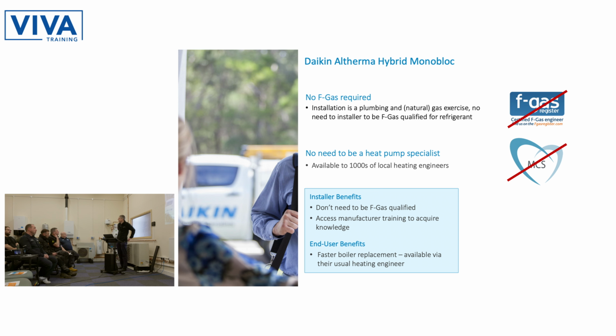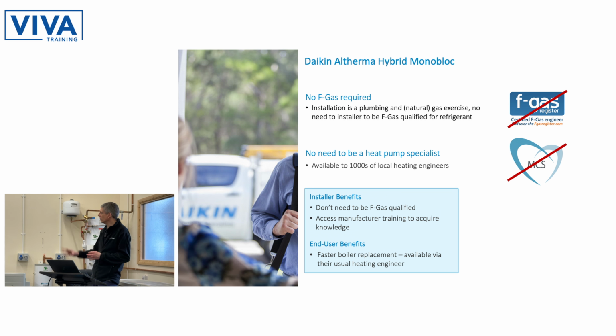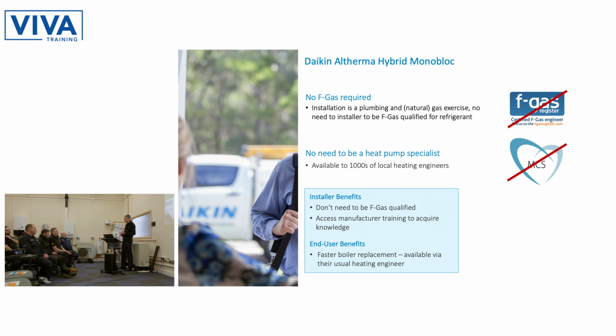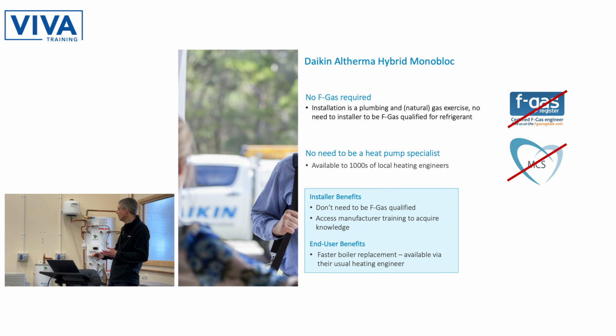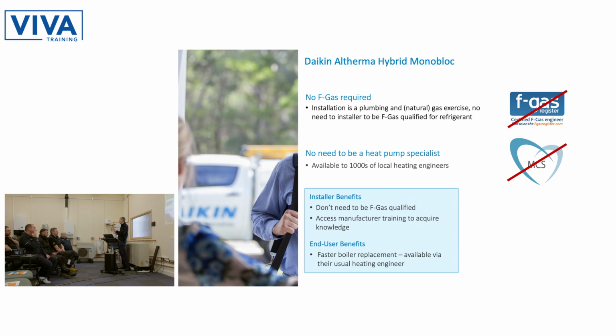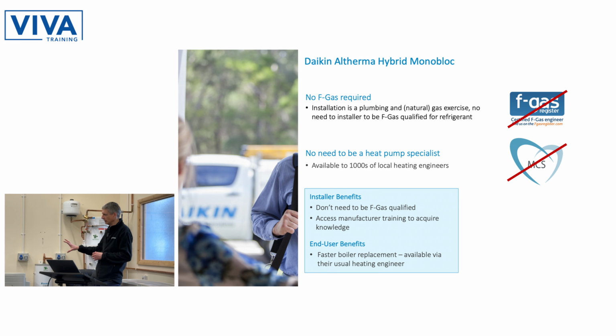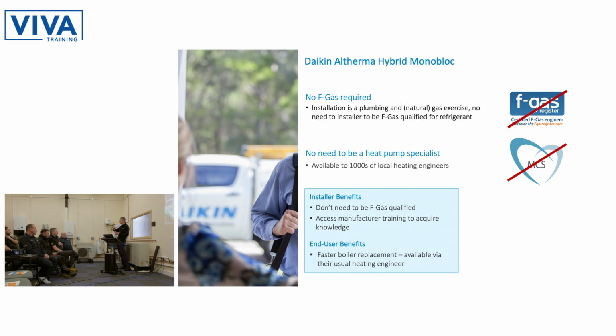It doesn't. No. It's what we call add-on. When you've got both of our components, we refer to that as our standard setup. We've also got an add-on setup. You can add that to an existing combi boiler system, but you don't get the hybrid operation. It will swap from heat pump to boiler, and you haven't got that bit in the middle where you can operate both, because another boiler can't talk to the heat pump to coordinate to get the best operation. The advantage is you can use any size heat pump then.